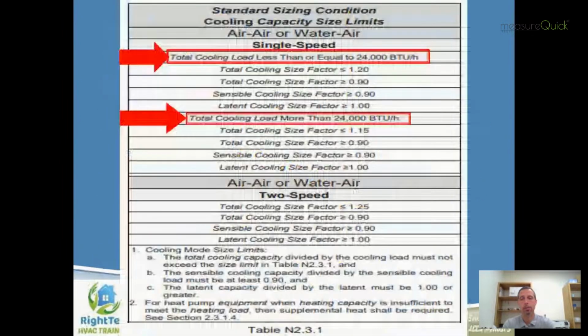So what I'm going to show you now is an excerpt from the new Manual S, talking about what we call the standard sizing condition for basic heat pump systems, and for cooling systems for that matter. And basically for a single stage unit, which unfortunately makes up about 85% of what gets installed across the country nowadays, the way that the old Manual S set that up, we had a maximum oversizing limit, for lack of a better word, of 15% for a single stage, 20% for a two-stage system, and 30% for a variable speed or variable capacity system.